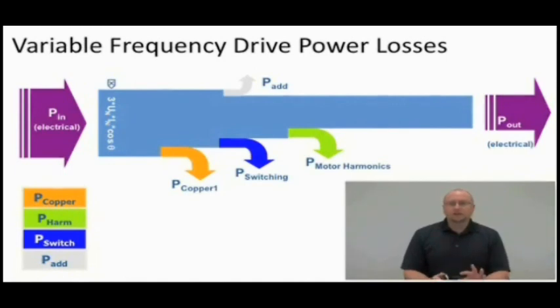And a little lesser known fact is that inverters also introduce some harmonic losses to the motor. That actually decreases the motor efficiency. So we'll talk about how that affects my overall system as well.